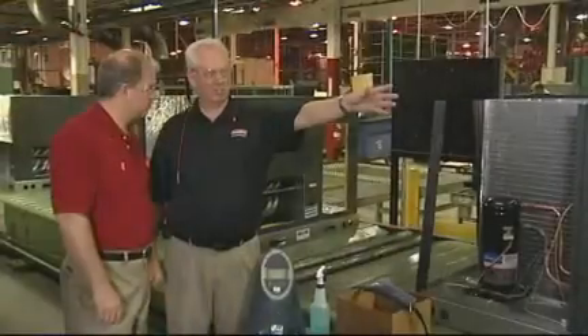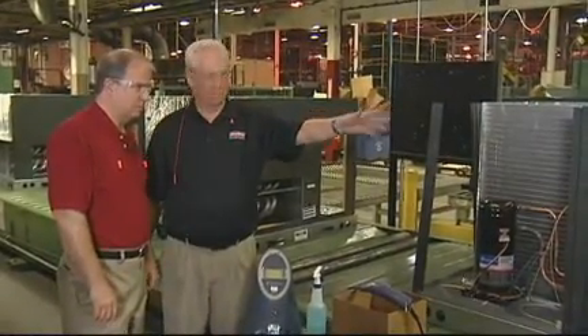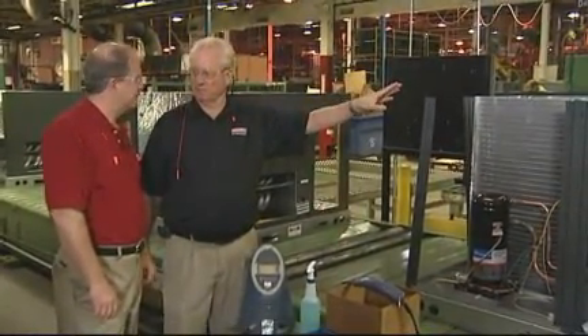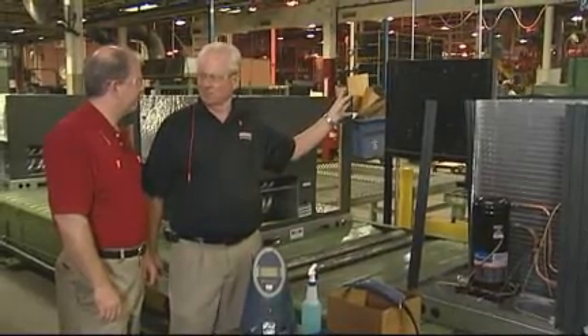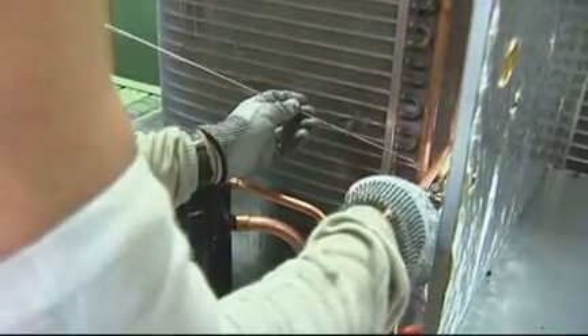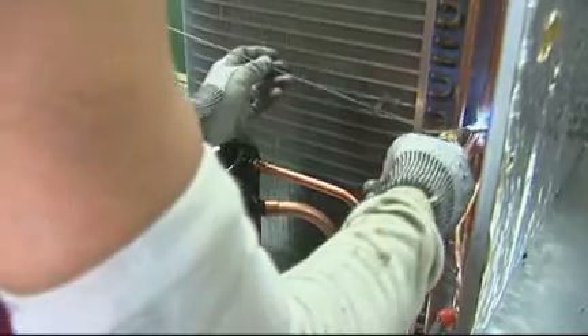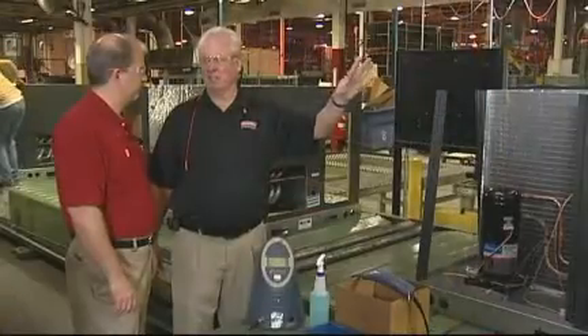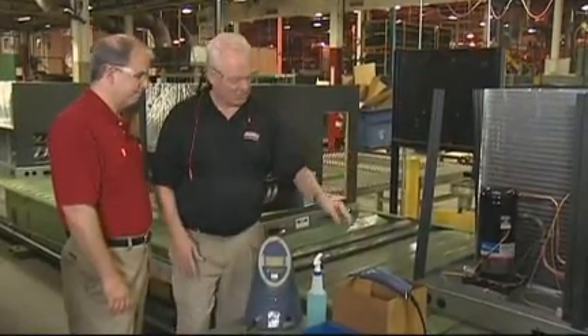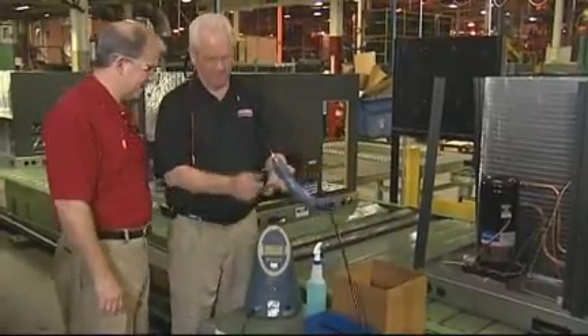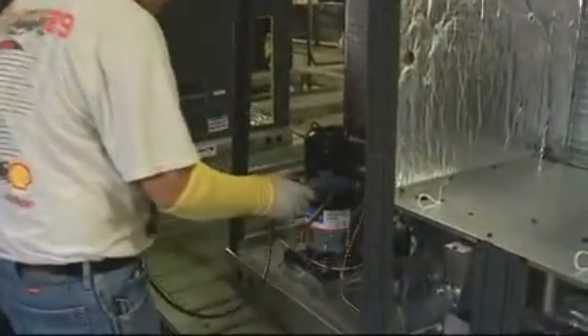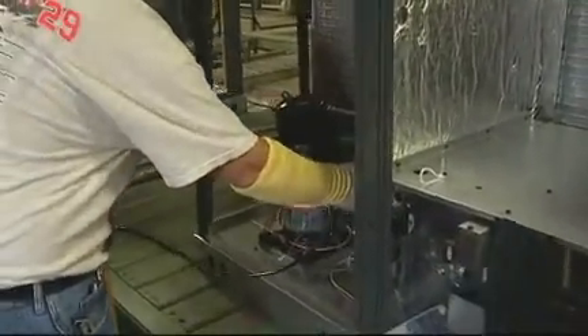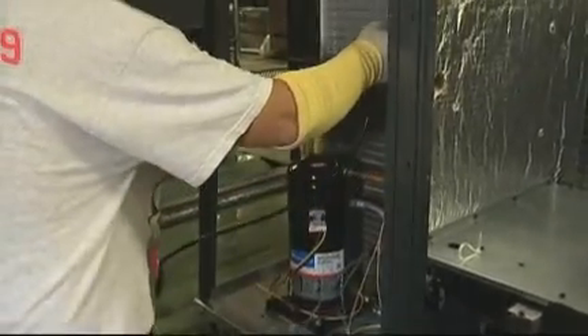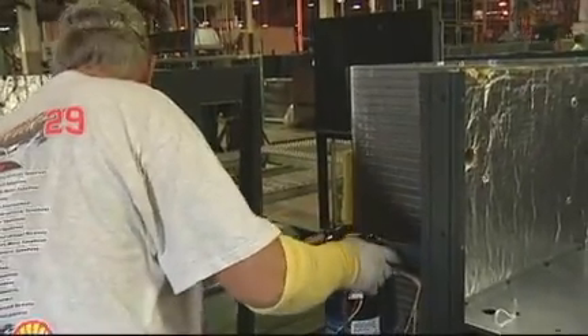Okay, the unit has been charged with refrigerant, and the coils were tested for leaks in the coil shop. Right. But we did do some brazing along the line here. Right. And as you well know, a leak in a unit is a dead unit. So at this point, we have an online leak detector, and this operator goes by every single joint to make sure that that refrigerant system doesn't have a leak in it.